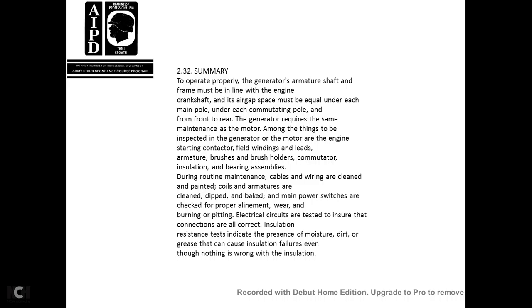Summary. To operate properly, the generator armature shaft frame must be aligned with the engine crankshaft. The air gap space must be equal under the face of the main poles and under each of the commutating poles, from the front to the rear. The generator requires the same maintenance as the motor. Among these things are the inspection of the generator or motor at the engine, the starting contactor, field windings, leads, armature, brushes, brush holders, commutator, insulation, bearings, and assemblies. During routine maintenance, cables and wiring are cleaned and painted, and coils and armatures are cleaned, dipped and baked, and main power switches checked for proper alignment, wear and burning or pitting. Electrical circuits are tested to ensure the connections are all correct.